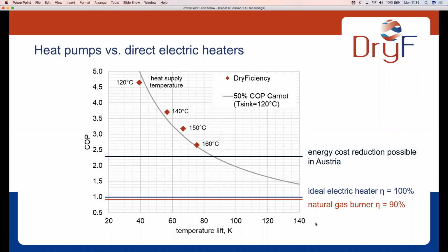And finally, there's a comparison of heat pumps and other direct electric systems. So as we've seen before, of course, there's a strong dependency of the efficiency of the heat pump on the temperature lift, so on the temperature difference between the heat source and the heat sink. And at one point, it might be more useful to use a direct electric heater than a heat pump. And this is what is shown in this diagram. So we have again the line for the ideal heat pump with 50% second law efficiency in gray. And whenever the COP is higher than the black line, energy cost reductions are possible with the Austrian prices that I've shown before. So in our case, if the temperature lift exceeds 85K, the cost will be equal and no more savings are possible.